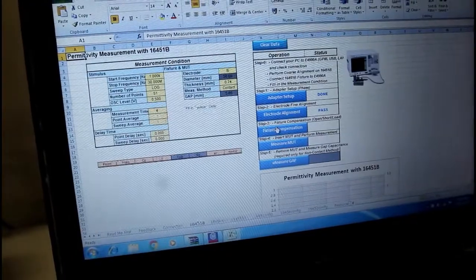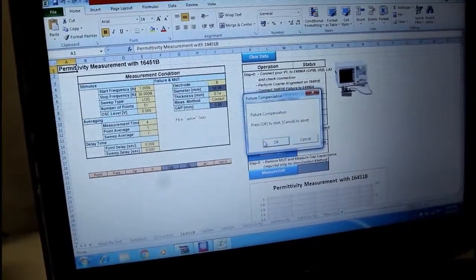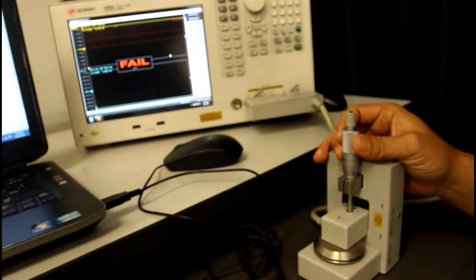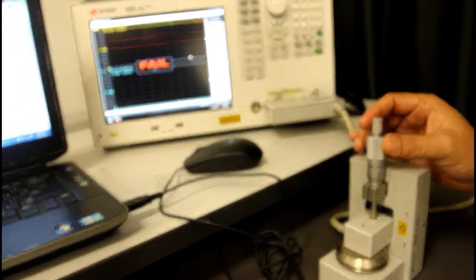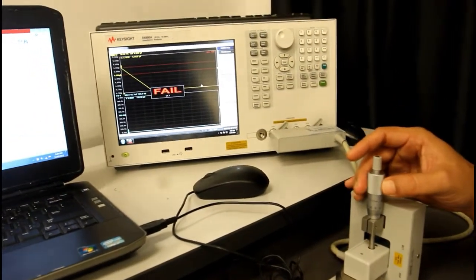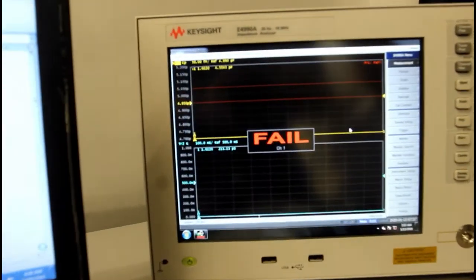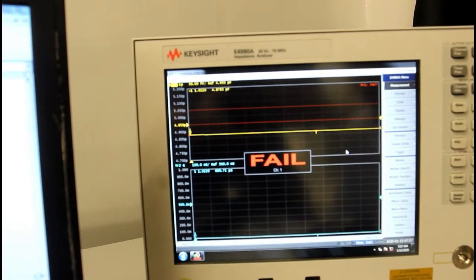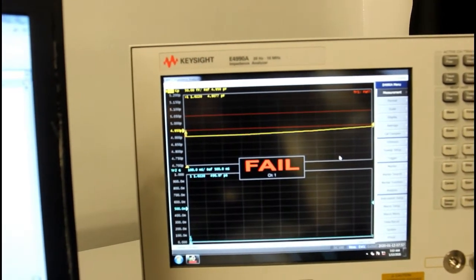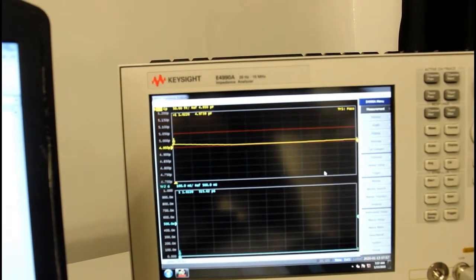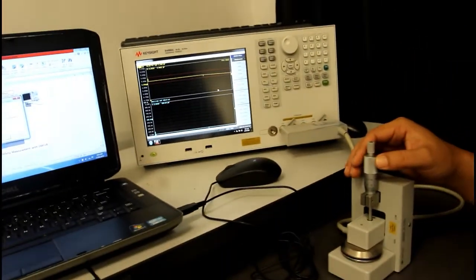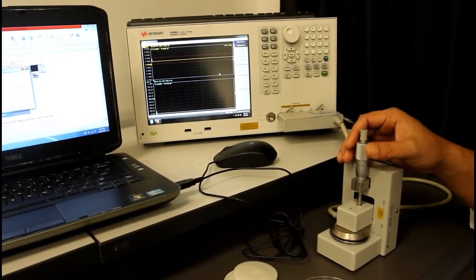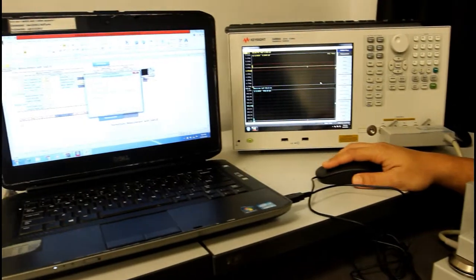Now, on the next step, just click on the fixture compensation. So, once again, you will have to do a similar step. But this time, as you can see, the yellow line is at the top of the screen. So, once again, tune the fixture until it is positioned in the between of the red line. Once again, the word of fail will disappear when the yellow is in the middle of the red line. Then click on OK in your laptop screen.